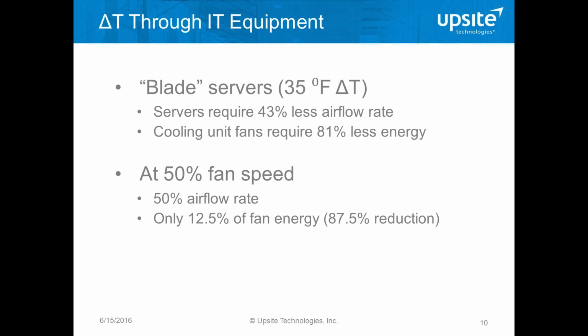The airflow requirement of 43% less airflow required by blade servers is not a linear cause for energy savings, but we actually take advantage of our fan affinity laws there, and we get a cube of that airflow savings translated into energy savings. The second bullet here kind of walks us through that math real simply as we look at if we're running our fans at 50% flow, we take 0.5 cubed, comes up to 0.125, so that translates to an 87.5% energy reduction, and so that's where the 81% energy savings in our example case study shows through.